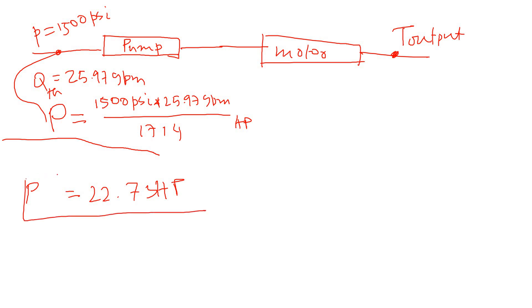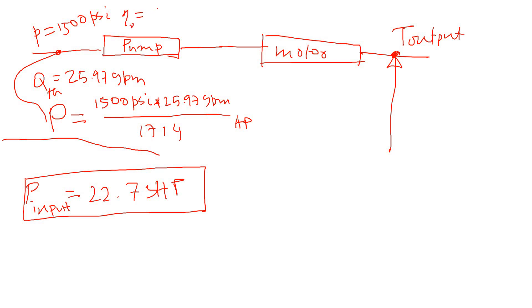That 22.73 hp is the pump input power. Now, to calculate the power output at the motor shaft, we have to account for all losses. The pump has two efficiency losses: volumetric efficiency of 85% and mechanical efficiency of 90%.